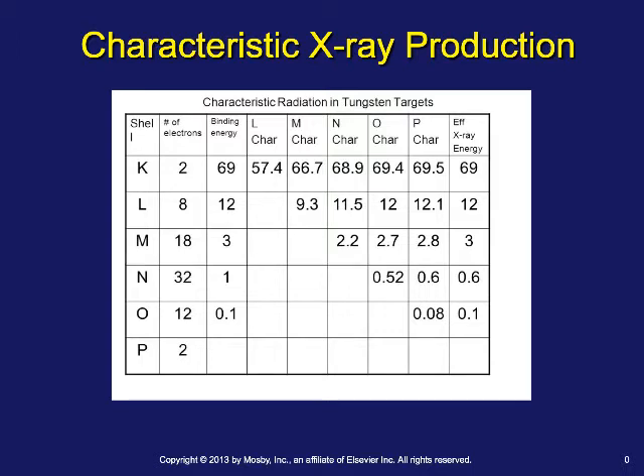For a tungsten target, the k-shell binding energy is 69 keV, so the x-ray produced from the loss of that electron is also 69 keV. There's a precipitous drop-off in energy from the k-shell to the l-shell at 12 keV. In terms of diagnostic uses, 69 keV is diagnostically useful but 12 keV is not, so we are only concerned with k-shell electron ejection for characteristic x-ray production as diagnostic x-rays. We filter the x-ray tube to keep those low energy x-rays from reaching the patient, because a 12 keV photon will only ionize the patient's skin with no diagnostic value.